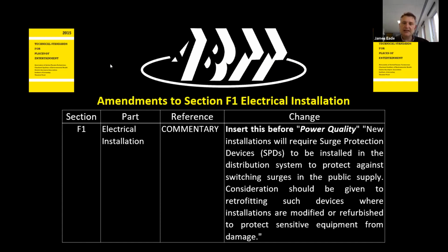Coupled with that, just in terms of Amendment 2, that section is changing, so we will see what is effectively a relaxation on that application for our industry. The wording around where SPDs are actually required has been reduced to situations where they are quite critical, and it's again designers' prerogative to design their system accordingly and decide if they think the installation warrants SPDs or not. So that's where we're at with those two.